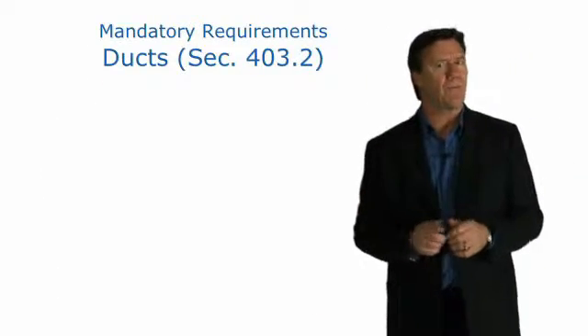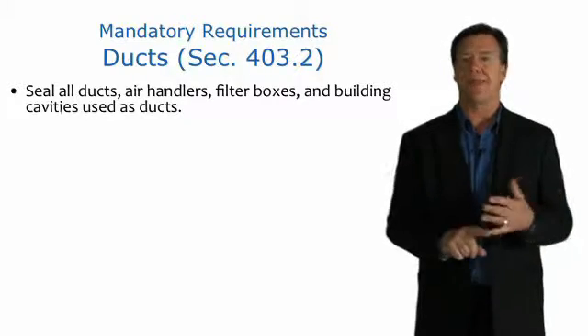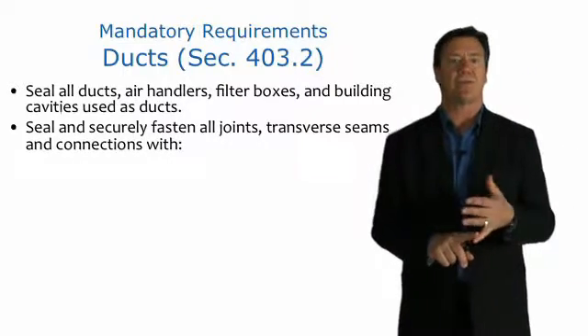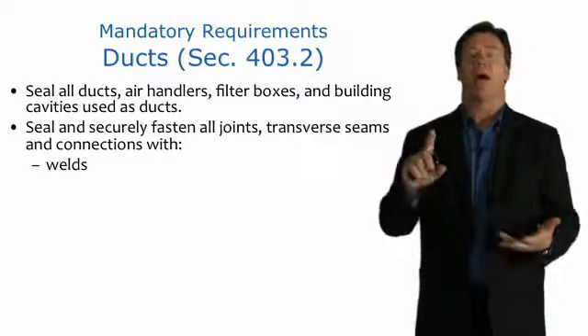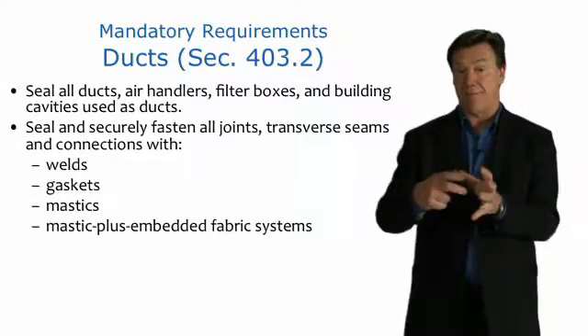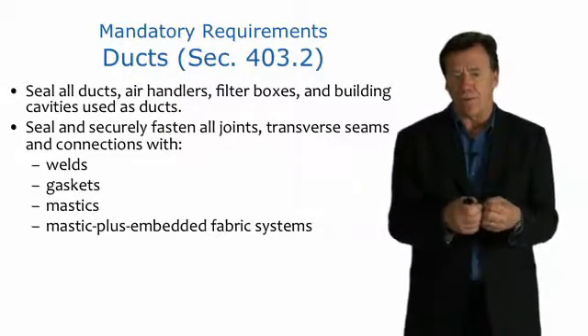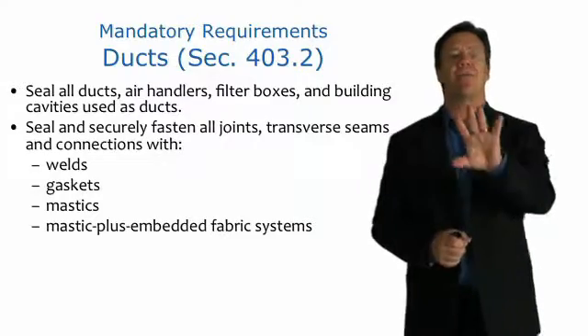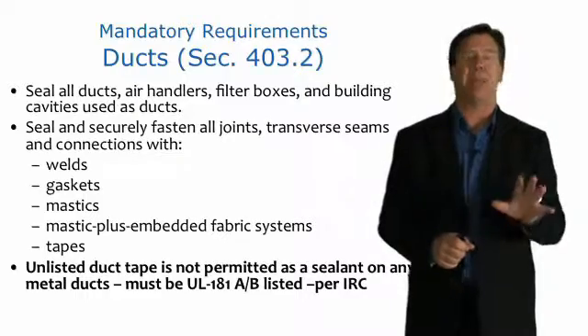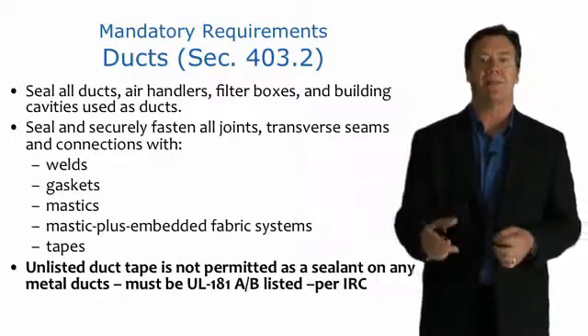With regards to Section 403.2, seal all ducts, air handlers, filter boxes, and building cavities used as ducts. We want to seal and securely fasten all joints, transverse seams, and connections with welds, gaskets, mastic sealants, or mastic plus embedded fabric systems — the latter for gaps too big for mastic to fill on its own — and the appropriate tapes. Unlisted duct tape is not permitted as a sealant on any metal ducts; the duct tape must be UL 181A or B listed per the IRC.